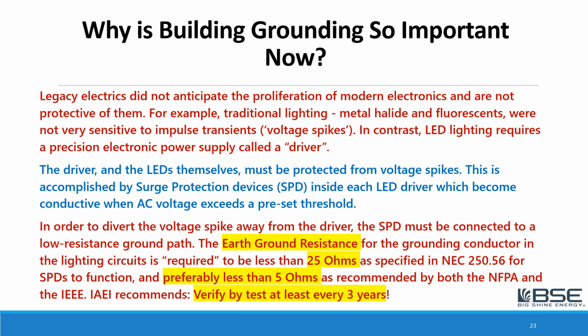So inside the driver of every LED fixture, there is a surge protection device, and it becomes conductive when the AC voltage exceeds a preset threshold. So that means there is a little protective device inside every one of these devices, whether it's an LED driver or any of the other equipment, a VFD drive. They all have some sort of circuit protection, but there's a limit to how many times you can hit them with impulse transients or spikes.